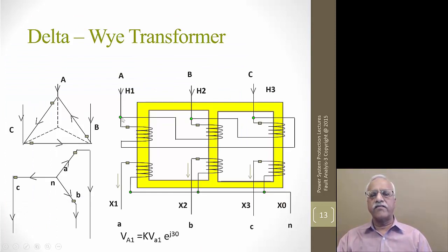One side is connected to A phase. Other side, if you go back, it is connected to C phase. That is this winding. And then on the same limb, you have another winding on the low voltage, VA, that is seeing the same flux. So it is the rate of change of flux which produces the voltage. So these voltages will be in phase.